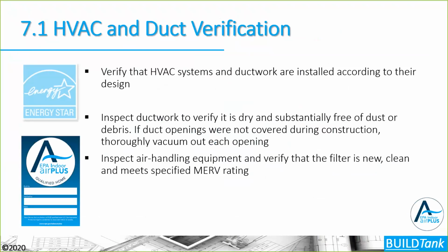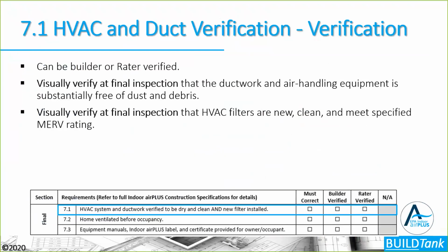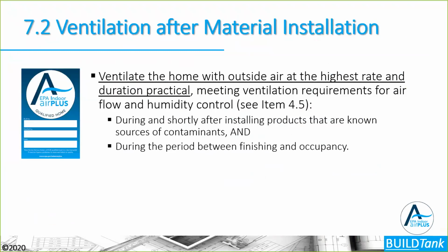So making sure that this part of the program gets implemented is super important because it's not something that's happening regularly out there in the field. Again, this is something that the rater would verify, usually verifying it at final through an inspection process here. Ventilation of the home with outside air at the highest ventilation rate possible before the house is turned over.